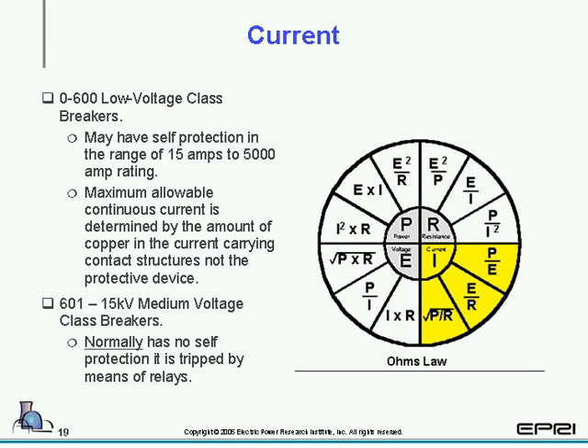Gene, this is Jim. Just to interject here, what Gene means by self-protection on a low voltage circuit breaker is what we call an overcurrent trip device. It's a part of the breaker, mounted on it, and that's typically only on the low voltage breakers. The medium voltage type breakers, 600 volts to 15 kV, don't have the overcurrent trip device as an integral part of the breaker. It's typically separate. It's usually an electromechanical relay, or solid state, or maybe even digital. So that's what Gene means by self-protection. Sorry for the interruption, Gene.